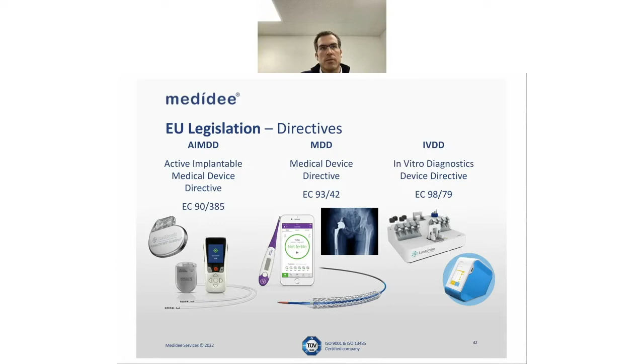Again, now we have two main regulatory frameworks, which replaced the previous organization. So we have 2017-745, which is the Medical Device Regulation. This regulation provides requirements with regard to basically every device, implantable, non-implantable, active, non-active, which is not an in vitro diagnostic device. And these include also specific requirements for software.